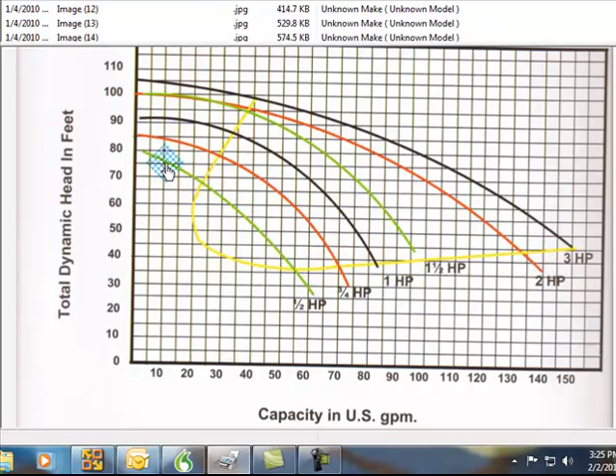I went before and talked about water flows to heaters. So, for argument's sake, we had a 400,000 BTU Sta-Rite heater, and we had, say, 90 feet of head. Would a half-horsepower pump do minimum, when everything's perfect, 40 gallons a minute? That's minimum, guys. So, you go, okay, I got 90 feet of head.